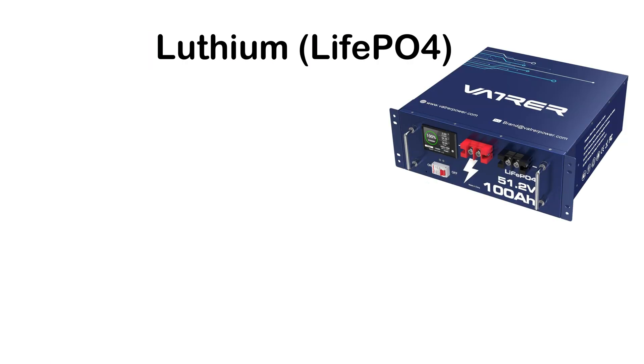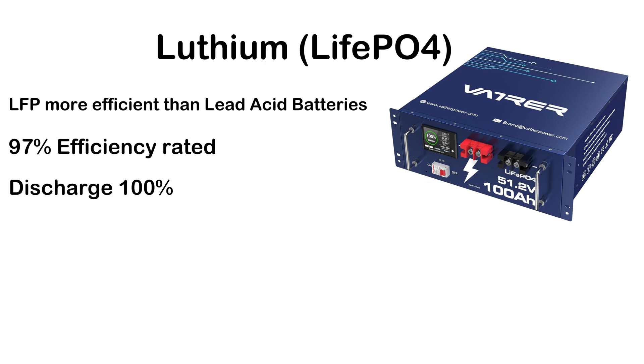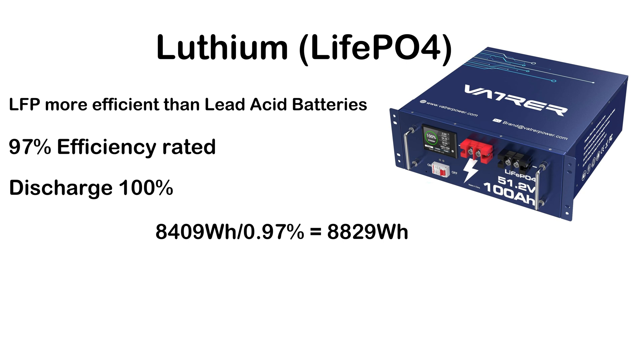We will use lithium iron phosphate (LFP or LiFePO4) batteries, which are more efficient than lead acid batteries. They are about 97% efficient. You can discharge them down to 100% depth of discharge, and after 6,000 cycles they still have 80% remaining capacity. To calculate: 8,409 watt-hours ÷ 97% efficiency = 8,829 watt-hours required.